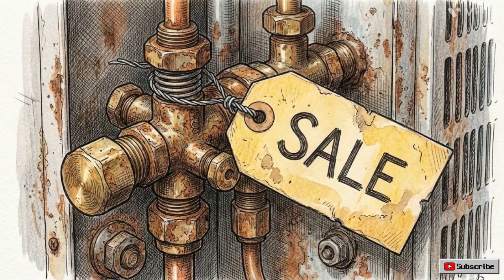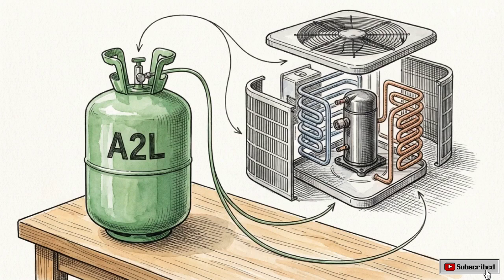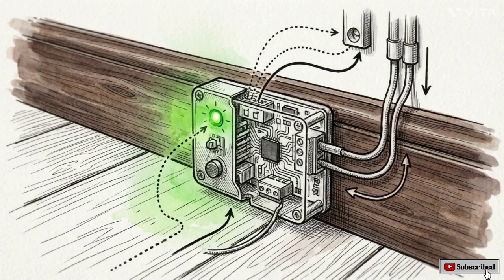Buying a discounted R410A system today is an economic trap. As the phase-down continues, the scarcity of the refrigerant will make future leak repairs exorbitantly expensive. The industry solution is a transition to next-generation A2L refrigerants. These achieve regulatory compliance and guarantee that your system remains repairable in the future. A2Ls are officially classified as slightly flammable. In practice, strict new building codes and equipment sensors make them incredibly safe for residential use.